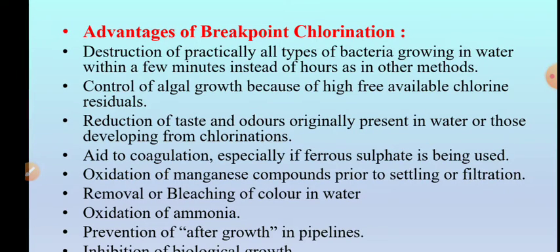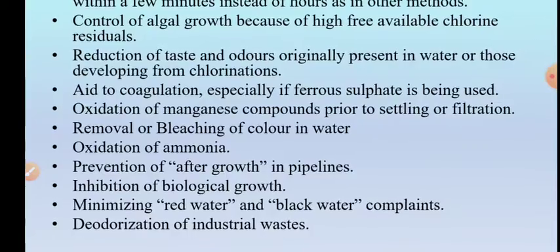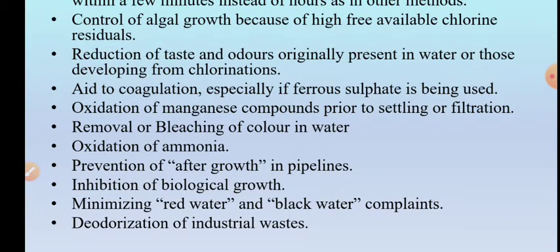Now, what are the different advantages of breakpoint chlorination? Number one, destruction of practically all types of bacteria growing in water within a few minutes instead of the hours that are required in other methods. Because you go on adding chlorine in increasing amounts, almost all types of bacteria are killed. Control of algal growth because of high free available chlorine residuals. Reduction in the taste, odor, and color which is originally present in water, or which arises because of a small amount of chlorine added. It helps in coagulation, especially if ferrous sulfate is used as a coagulating agent.